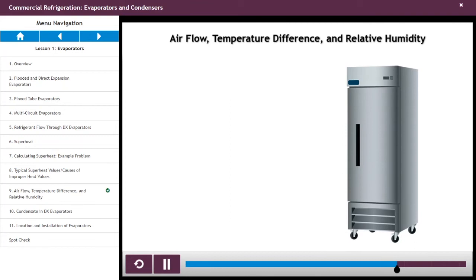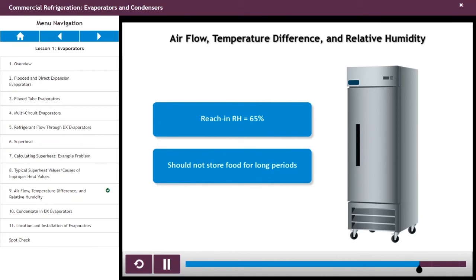A reach-in with a higher TD has a lower humidity of 65%. The relatively low humidity of a reach-in means that food dries out more quickly than in a walk-in, and should not be used to store food for long periods.